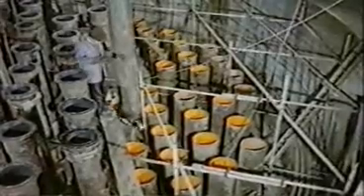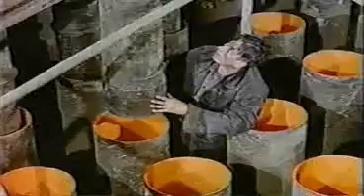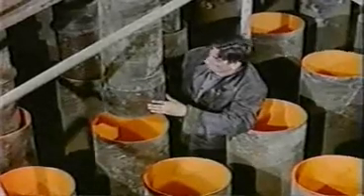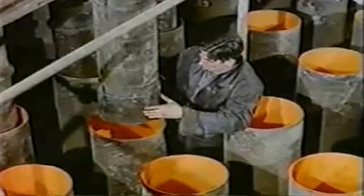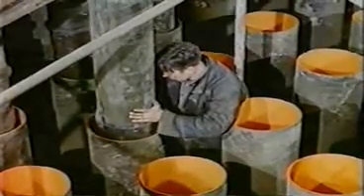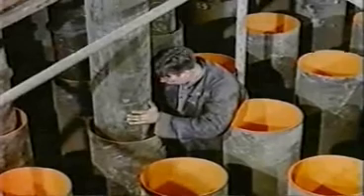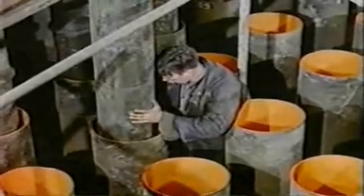Some while later, on the reactor operating floor above the thermal dome, the standpipes are being fitted. These are guide tubes through which the charge machine passes uranium fuel into the reactor. Some of them are used for the control rods that control the reactor. There will be 256 standpipes when finished. They pass through the thermal dome and link up with the openings in the top cap of the reactor vessel itself.